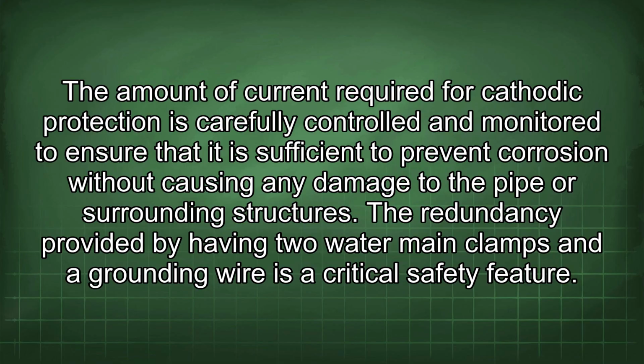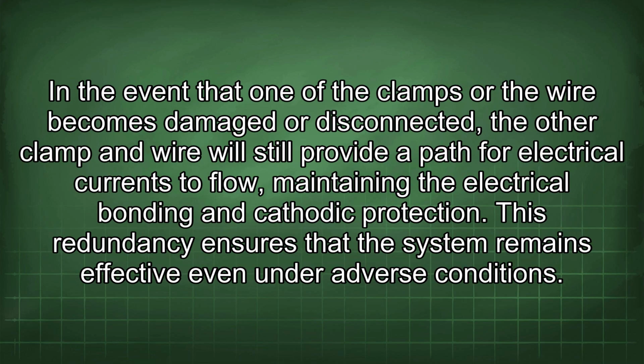The redundancy provided by having two water main clamps and a grounding wire is a critical safety feature. In the event that one of the clamps or the wire becomes damaged or disconnected, the other clamp and wire will still provide a path for electrical currents to flow, maintaining the electrical bonding and cathodic protection. This redundancy ensures that the system remains effective even under adverse conditions.